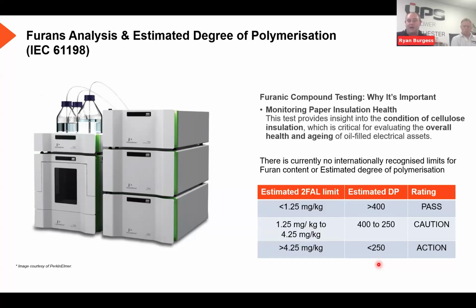At this point, this is where you then need to start thinking about upping your frequency of testing. So if you're testing every 2 years, you'd want to consider upping to every year to carry on monitoring. And then once you get to the 250 or lower, again, there's different levels even past that. And when you get to the action, you need to start planning for the end of the asset's life. And during that period, from caution to action, you also need to consider managing the load of an asset.